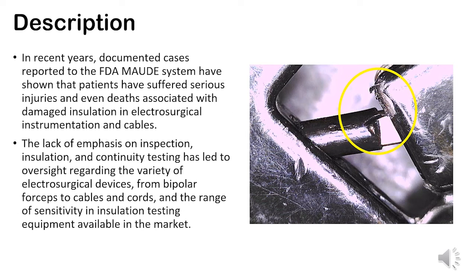For the description, in recent years there have been documented cases reported in the FDA MAUDE reporting system. This has shown patients have suffered serious injuries and even deaths associated with damaged insulation in electrosurgical instrumentation and cables. The lack of emphasis on inspection, insulation, and continuity testing has led to an oversight regarding the variety of electrosurgical devices, from bipolar forceps to cables and cords, and also the range of sensitivity in insulation testing equipment available on the market today.